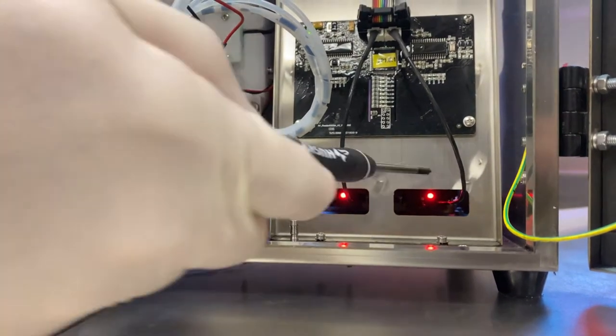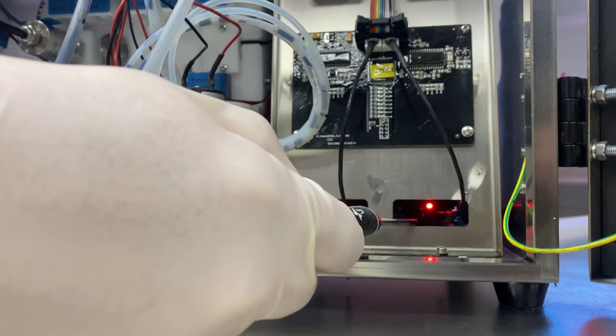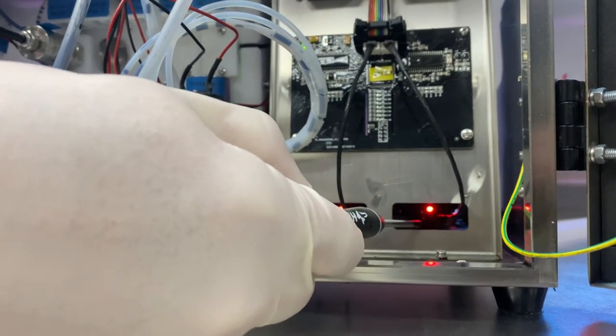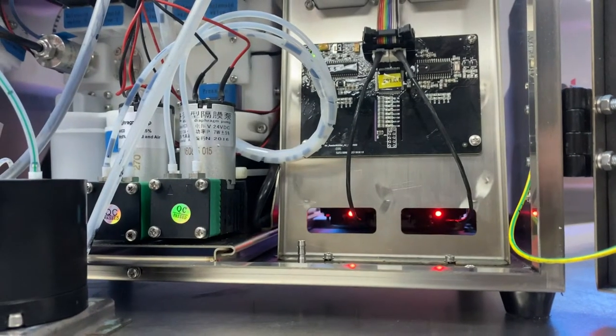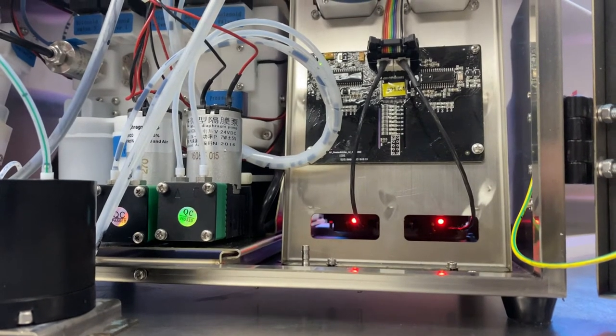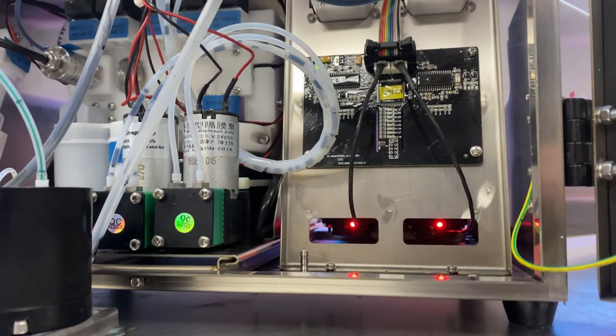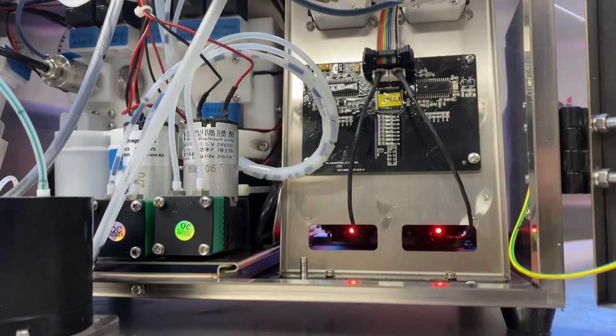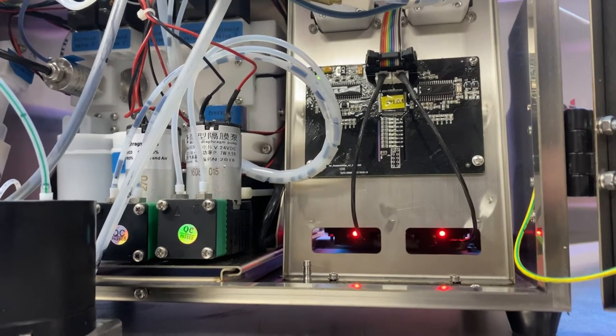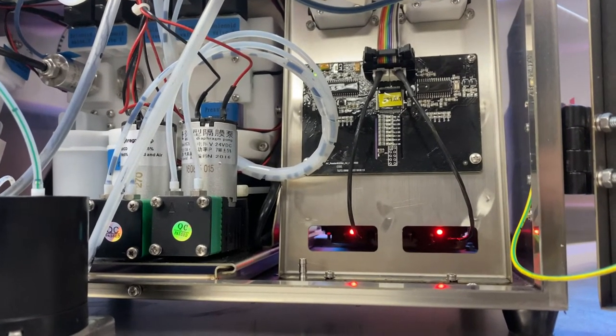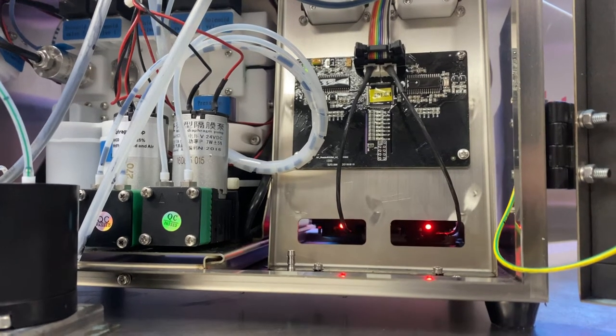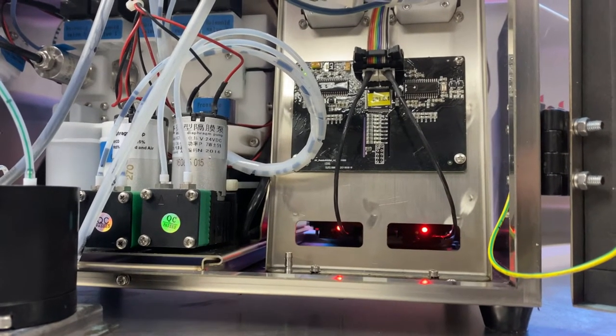Okay, so our red light has turned on. This is normally what we would expect to see if the cartridge has fluid in it. If the light does not come on when we insert a cartridge that does have fluid, there is a potentiometer that we can adjust to increase or potentially decrease the sensitivity of the cartridge sensor.